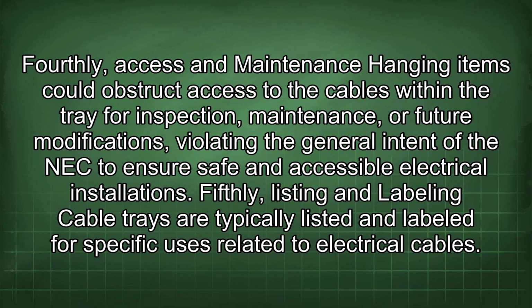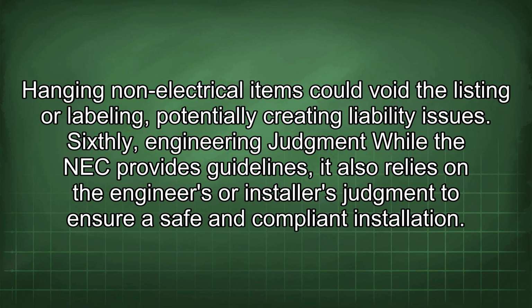Fourthly, access and maintenance. Hanging items could obstruct access to the cables within the tray for inspection, maintenance, or future modifications, violating the general intent of the NEC to ensure safe and accessible electrical installations. Fifthly, listing and labeling. Cable trays are typically listed and labeled for specific uses related to electrical cables. Hanging non-electrical items could void the listing or labeling, potentially creating liability issues.